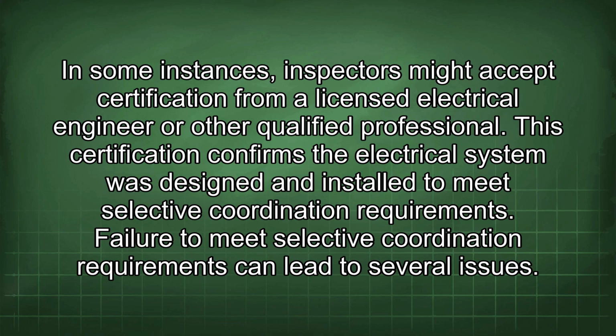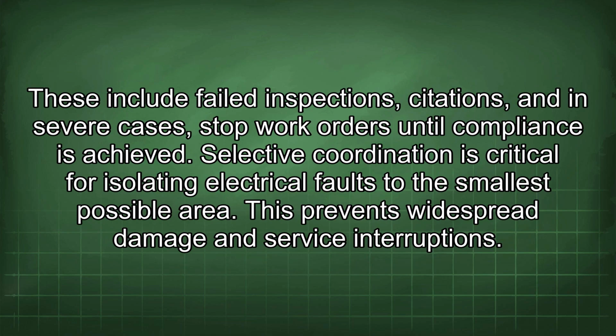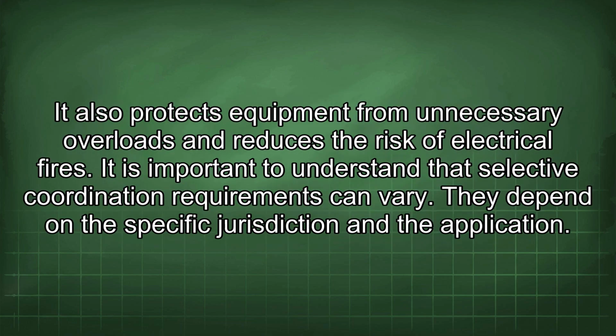Failure to meet selective coordination requirements can lead to several issues. These include failed inspections, citations, and in severe cases, stop work orders until compliance is achieved. Selective coordination is critical for isolating electrical faults to the smallest possible area. This prevents widespread damage and service interruptions. It also protects equipment from unnecessary overloads and reduces the risk of electrical fires.